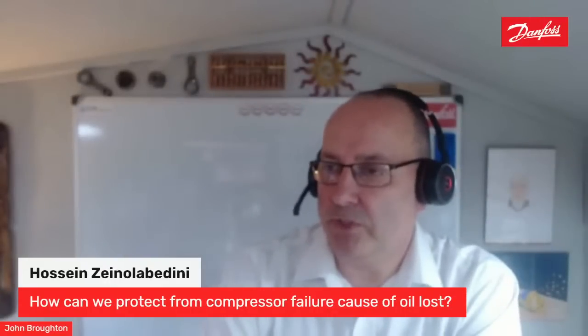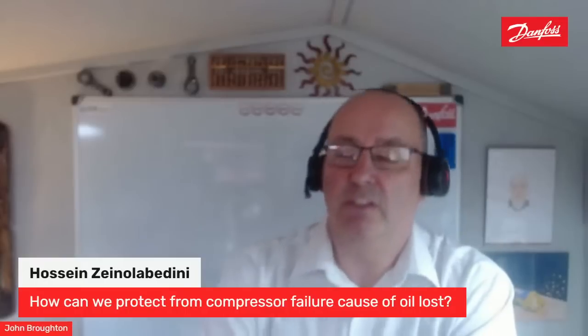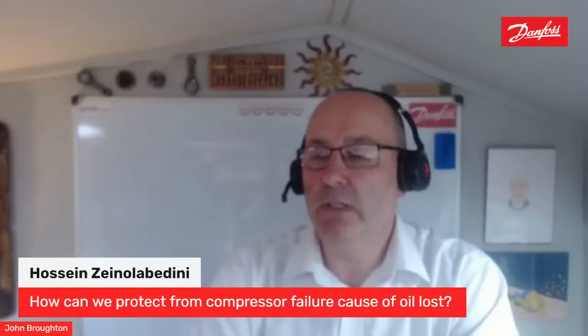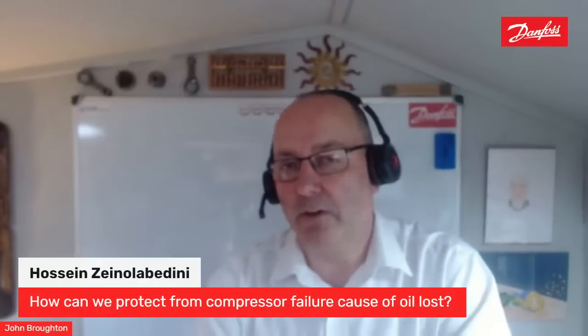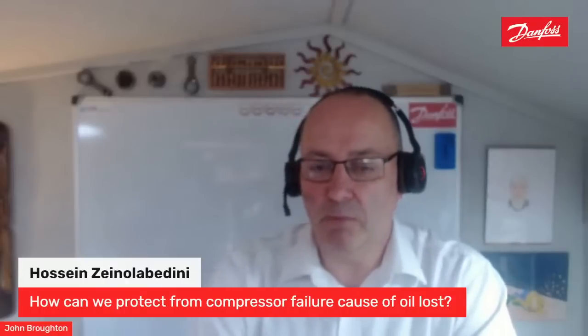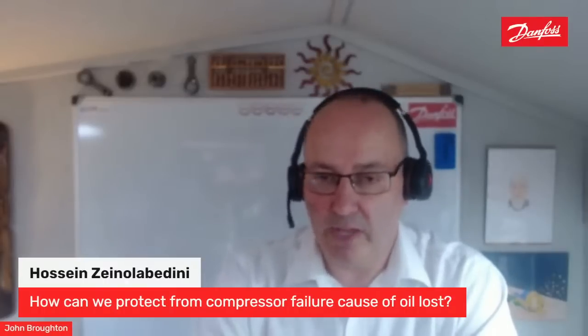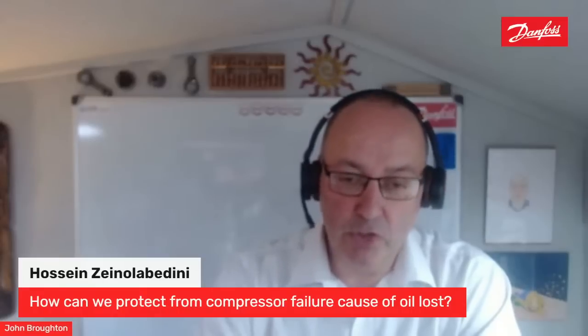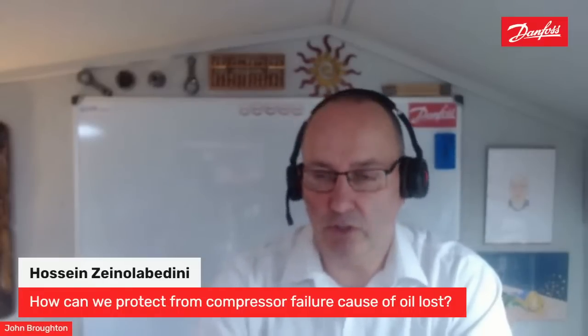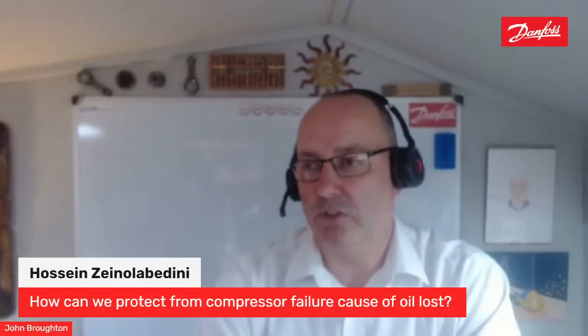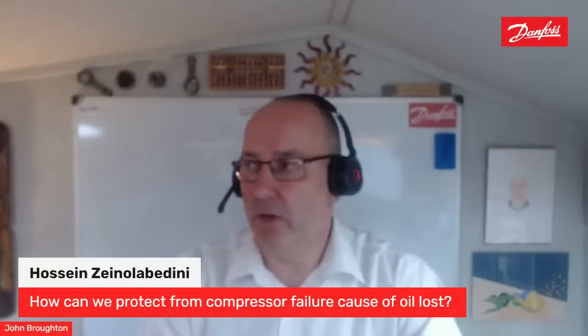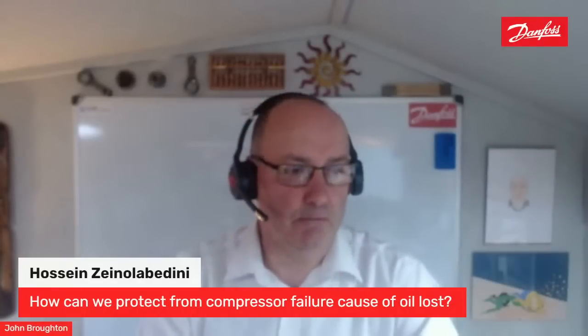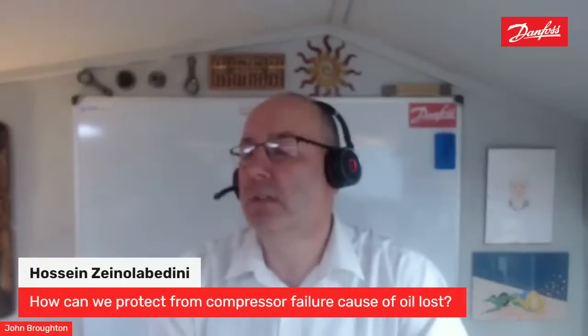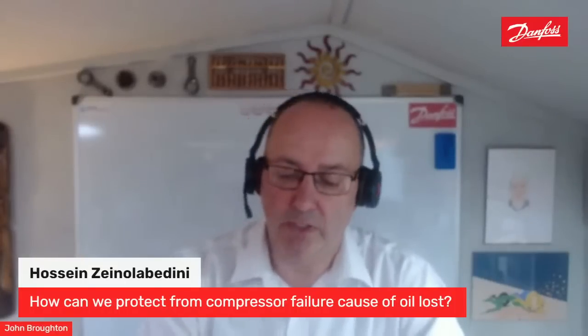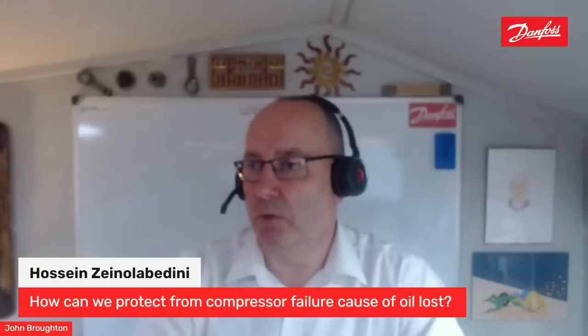The best way we can protect the compressor is to ensure that we have the right suction velocity, and this comes back to the discussions we've had before regarding the pipework. If we get the right velocity, we will get that oil back to the machine. If we keep the machine operating within its envelope, we will reduce the amount of oil carried over by the action of the compressor out the discharge line. If we operate at the extremities of the envelope, particularly in low pressure and very high pressure scenarios, that will cause more oil carryover, and by that I mean the oil will be entrained in the refrigerant by the action of the compressor, and that will be pumped out.